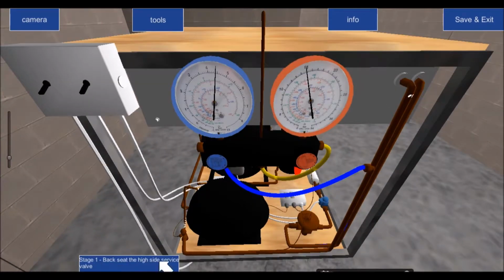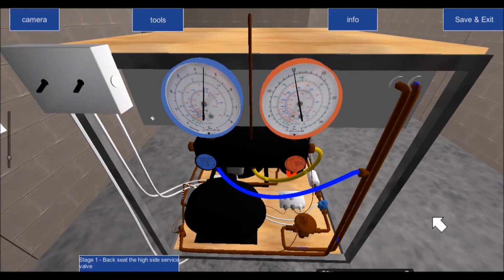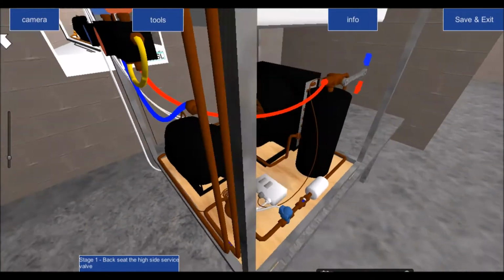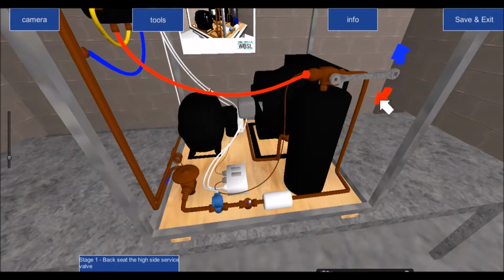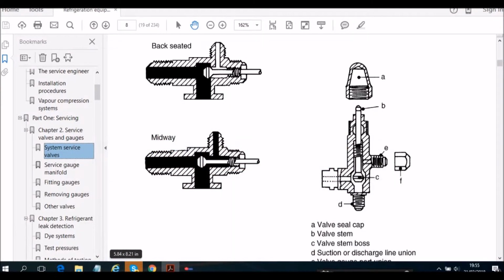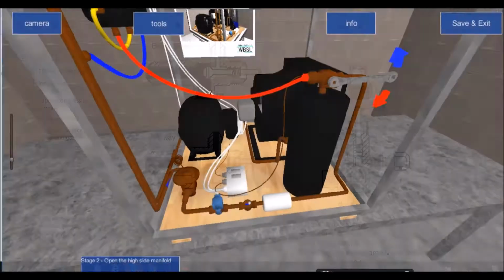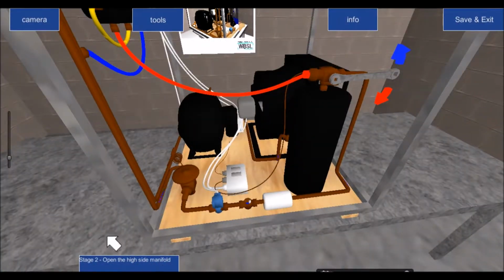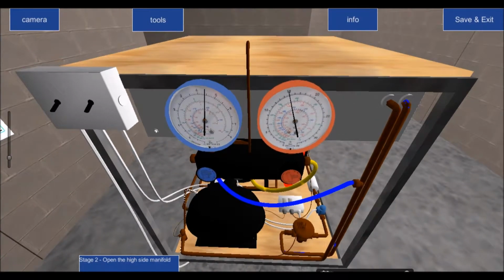Now, backseat the high side service valve. So effectively I'm backseating the valve like so. That basically means I've gone from this position and put it into this position, and by putting it into this position, no new refrigerant can now enter this area here. Okay? So the next thing it says, open the high side manifold. So effectively I'm opening the manifold here.